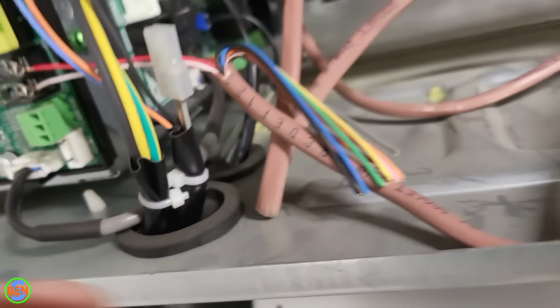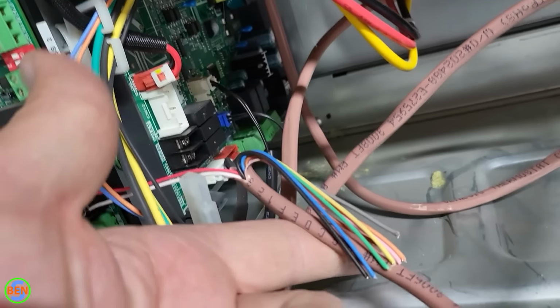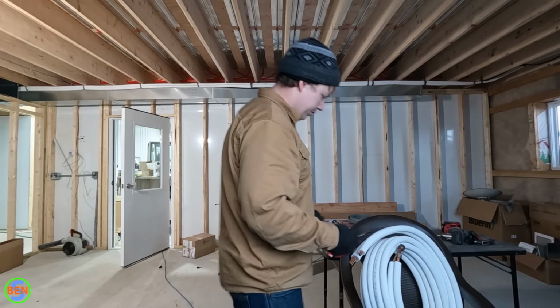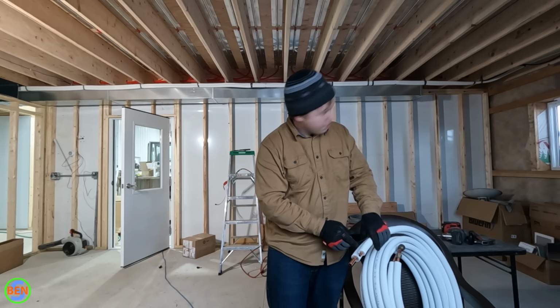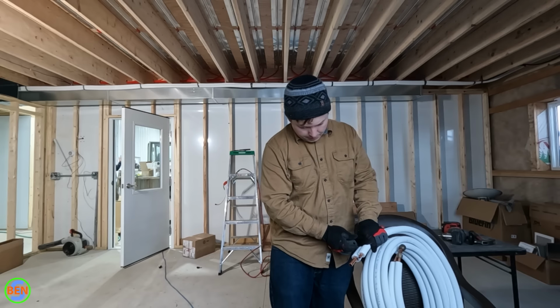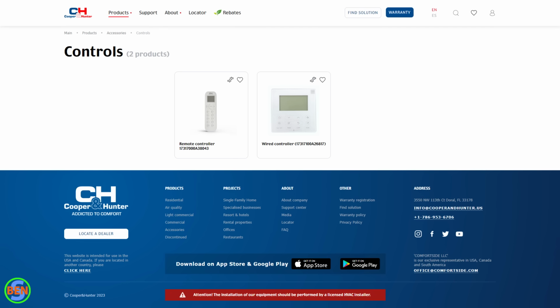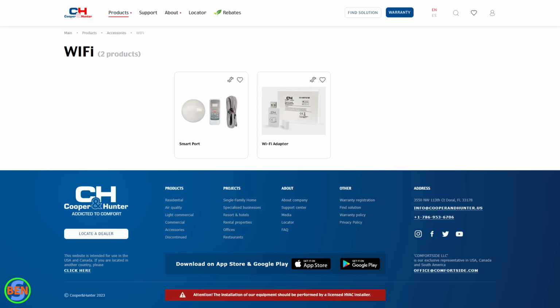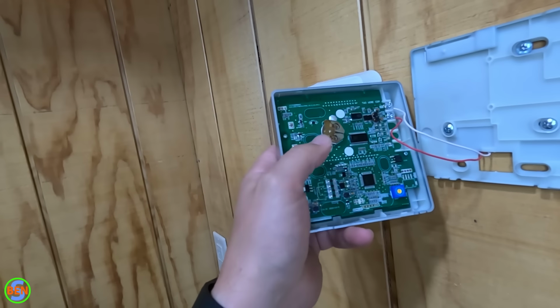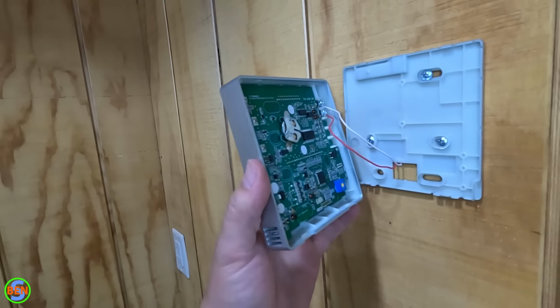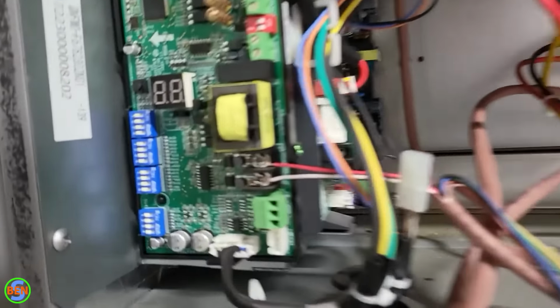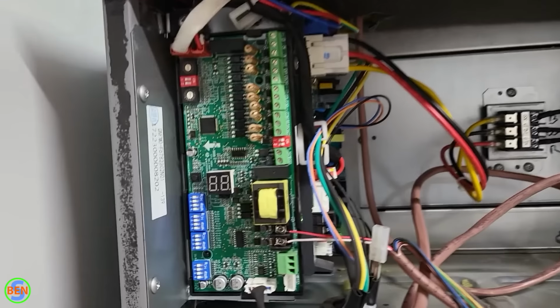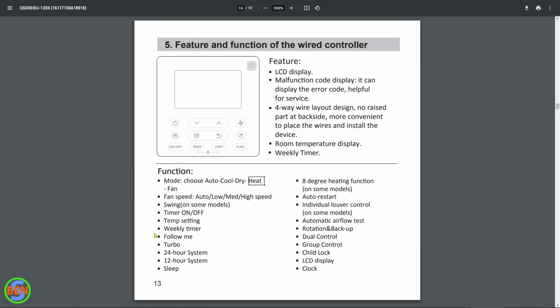The only other wiring detail that is involved is that we did actually pull a thermostat wire from the air handler unit to the office, which is what will be controlling our air handler. Now, they do offer different wireless solutions as well, so if you are interested in having more of a traditional remote style, I believe there's a way to make that happen as well. Personally, for an air handler, I would rather have a regular wall-mounted thermostat anyway, and so that's what we went ahead and did. The included thermostat actually only needed 2 wires to communicate back to the air handler, even though it has a whole bunch of different functions that it is able to perform, which is pretty cool.